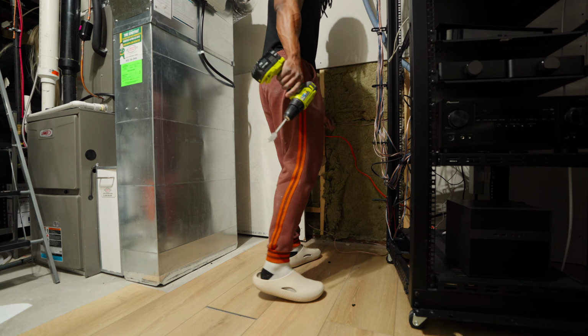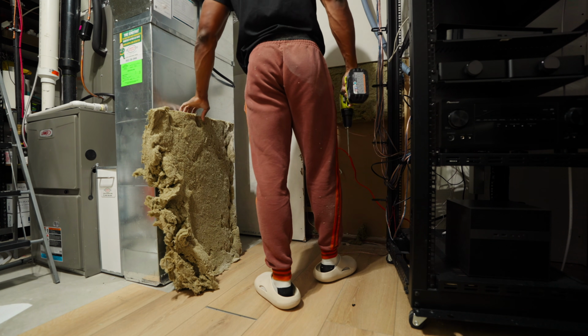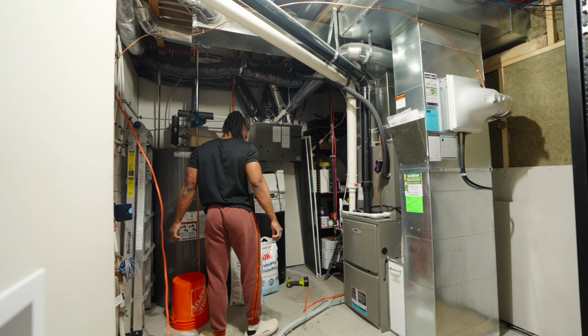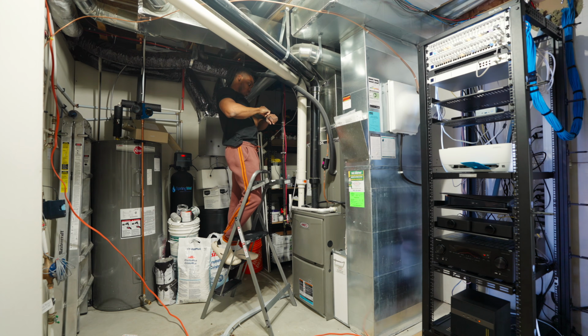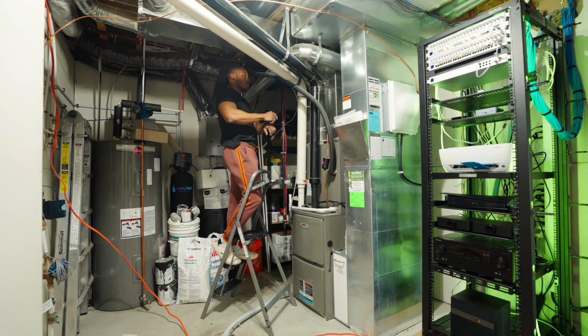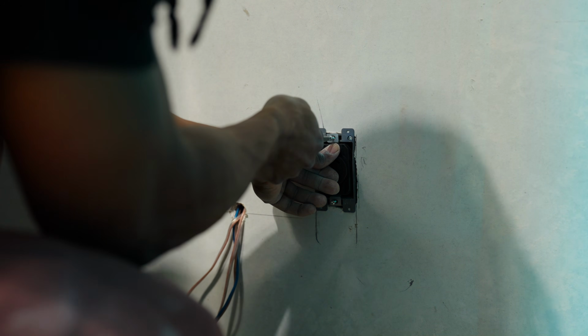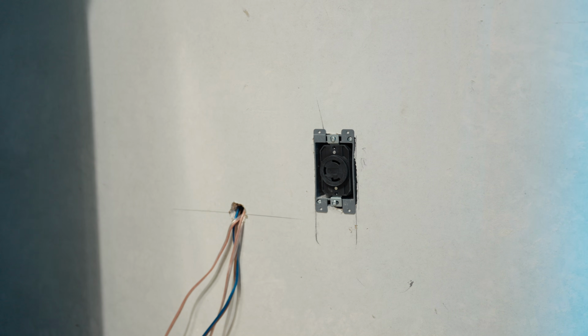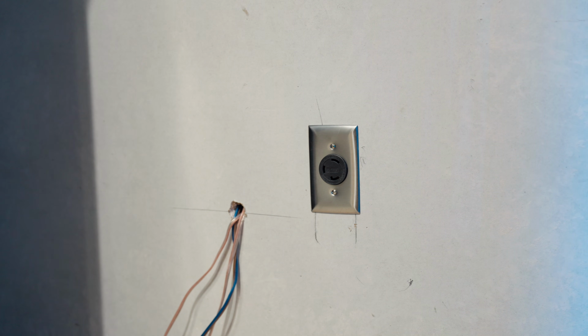After the rack was built, we opened up the drywall and ran the wires from the rack location back to the electrical panel, then had an electrician install an L5-30R receptacle on a single pole 30-amp breaker, which is the correct setup for a 120 volt, 30-amp circuit.